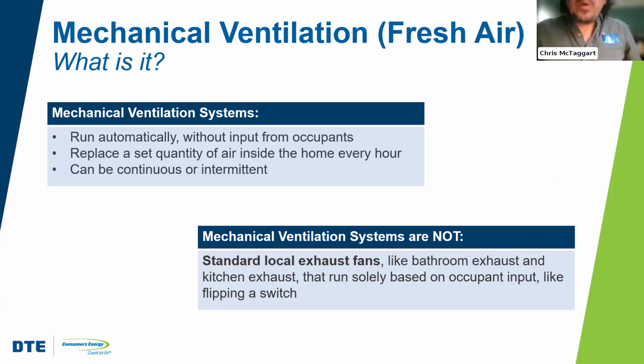Okay, so moving away from heating and cooling systems to mechanical ventilation. This is one of the other, I'd say, big value propositions of Energy Star. You could say, well, aren't homes by code required to have mechanical ventilation? And they are, but getting the specifics of that, especially in the state of Michigan, I've found not everybody quite understands how to implement it properly. So mechanical ventilation systems by Energy Star have to be set to run automatically without the occupant intervening. And they're going to be either continuous or intermittent.